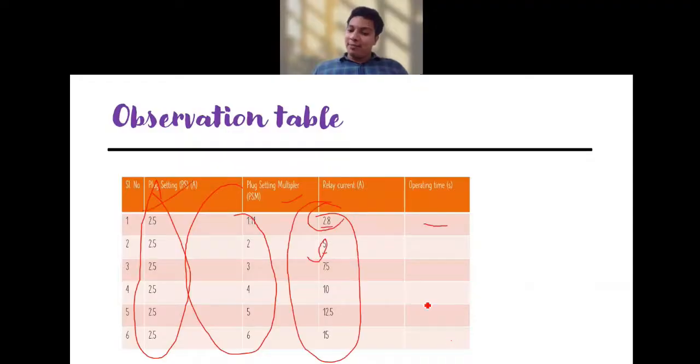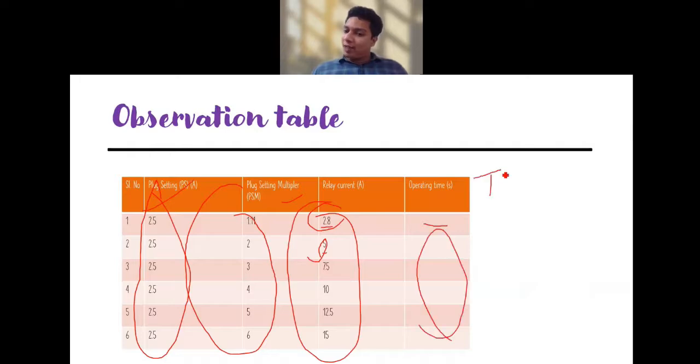With respect to plug setting, you apply the plug setting multiplier values and note the relay current values. The relay current means whatever input current we are giving - we will vary this relay current and observe the operating time needed. Plug setting is set, and plug setting multiplier is chosen based on the relay current. We apply different relay currents - 1.1, 2, 3, 4, 5, 6 - and note down the operating time for a particular TMS value. We will take three TMS values and I will share the lab manual.